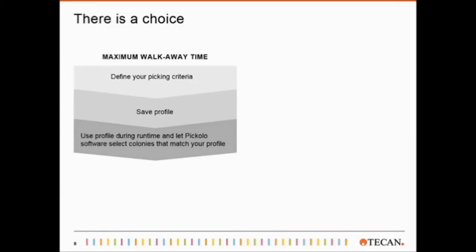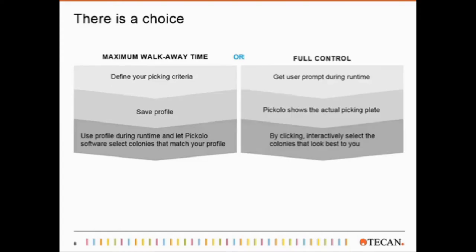Either you define your colonies and save the criteria in a picking profile, which is then called up automatically during the picking process, and the robot chooses and picks the colonies accordingly, which gives maximum walkaway time. Or you stay in control - the robot shows a picture of your plate during the run, and you can select each single colony that should be picked. This is almost like picking by hand, just with a system that does the tracing. But this way you have a chance to really pick the colonies that look best to you. So either pick colonies fully automated or pick the colonies that you like best.